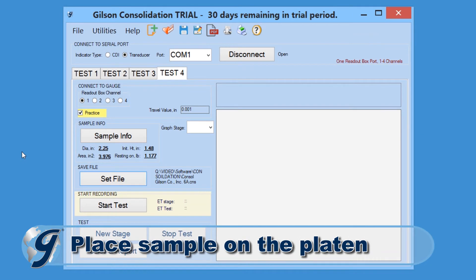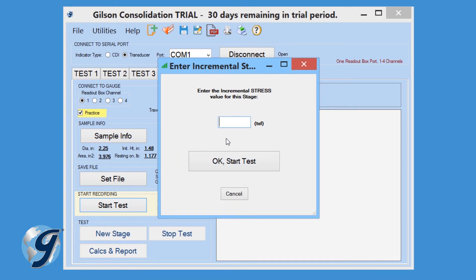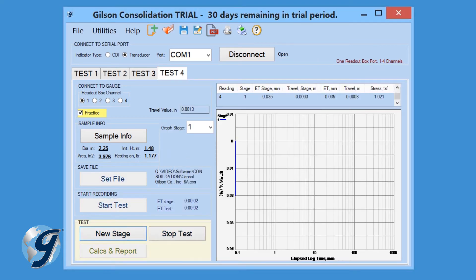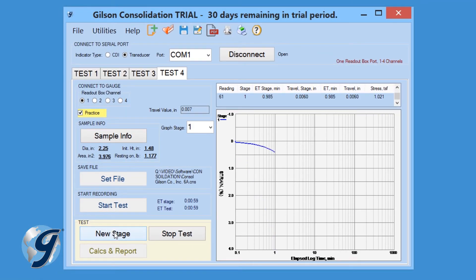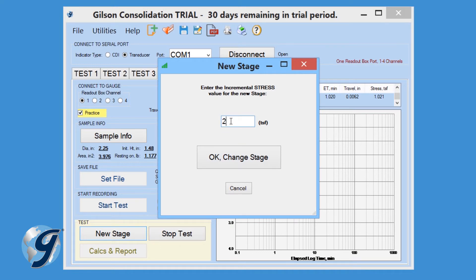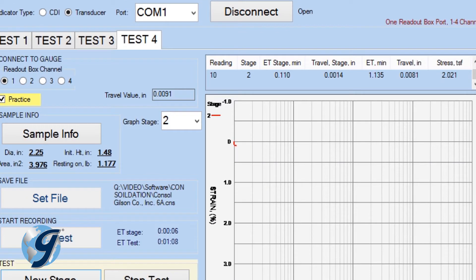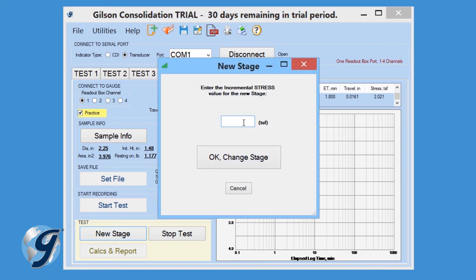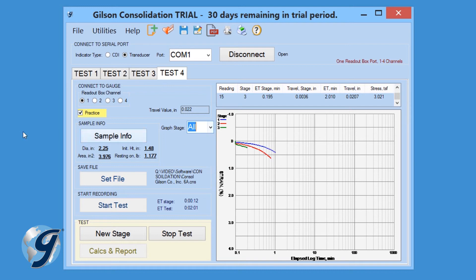Now position the specimen for testing on the testing device. Next, click Start Test and enter the stress value for the first stage. Once entered, select OK Start Test, then apply the load to the sample. Readings will be displayed in real time when the load is applied to the sample. After the completion of the first stage, select New Stage, then enter the next incremental stress value. Once entered, select OK Change Stage and apply the next load to the sample. Repeat this step for each additional stage. You can select to watch test results in graph form in real time for each test stage or for all stages.